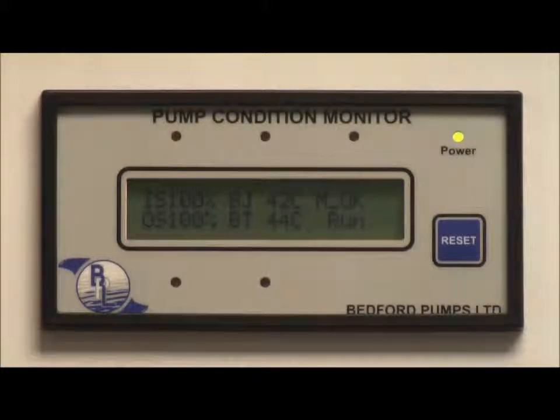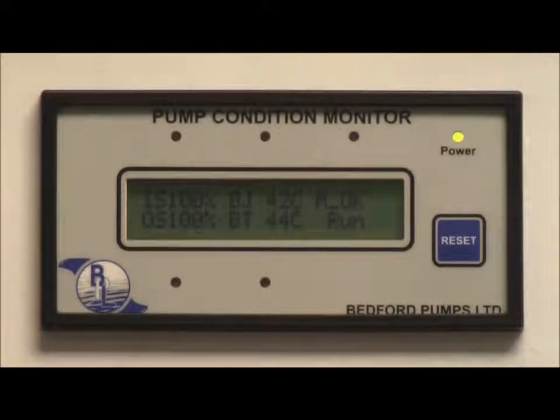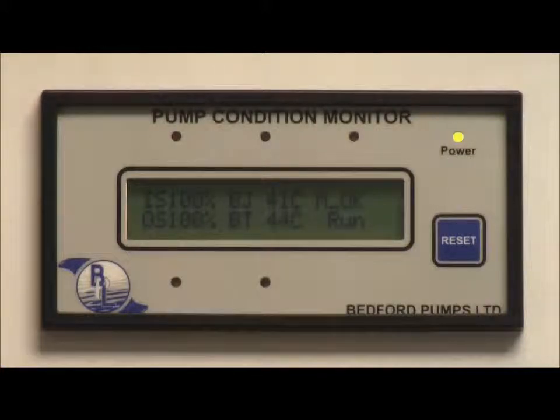The seal monitoring section will indicate the integrity of water barriers, giving a visible display of current status. Bearing temperatures are indicated. The pump will alarm or trip if preset limits are reached. Cable short or open circuits are detected, indicated and alarmed.